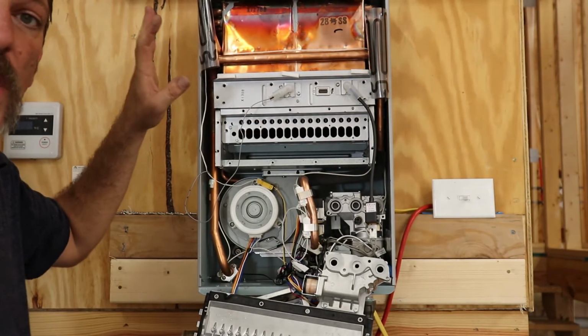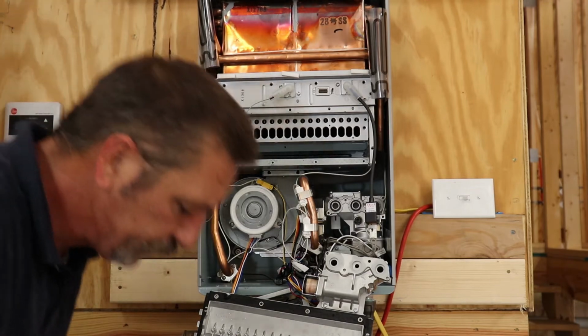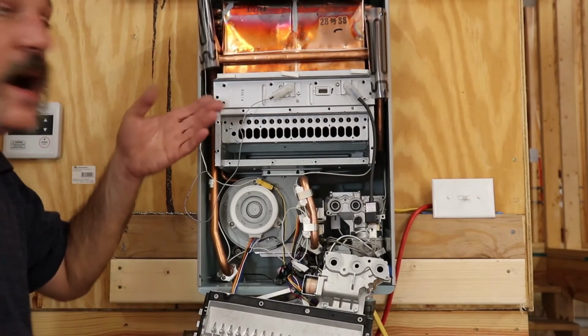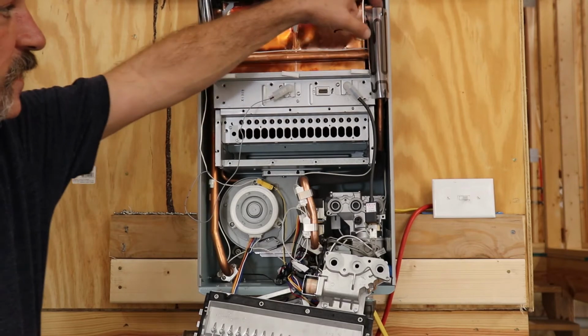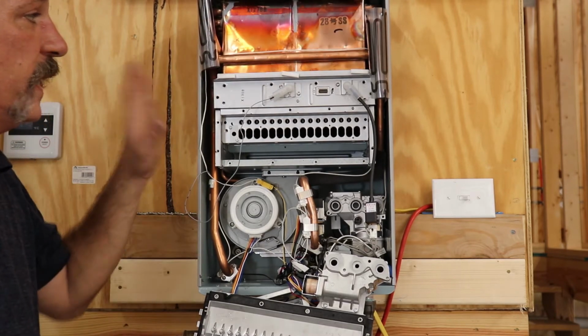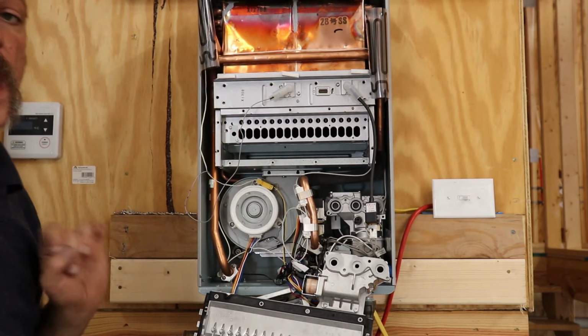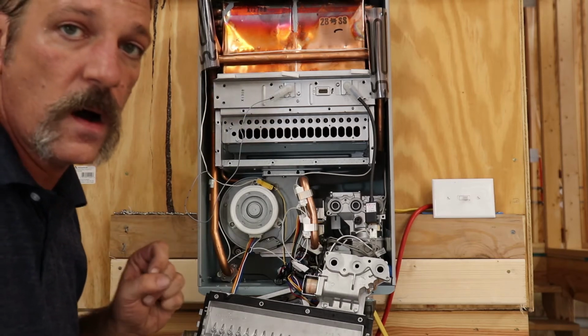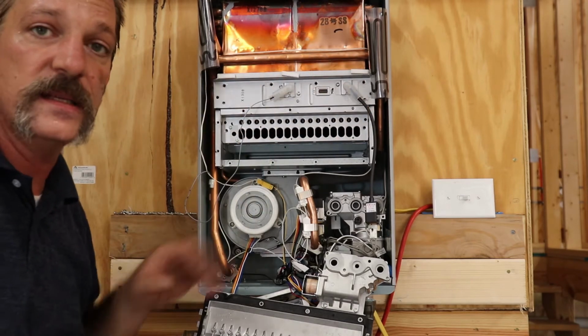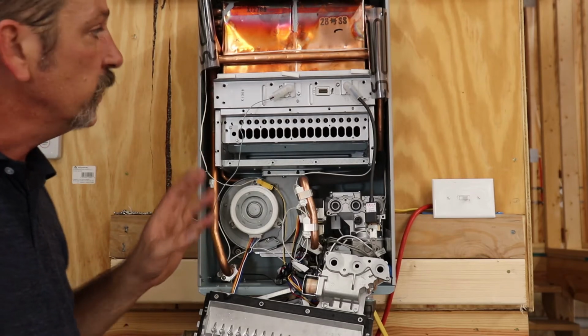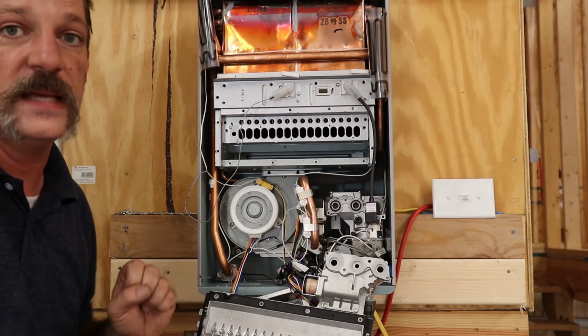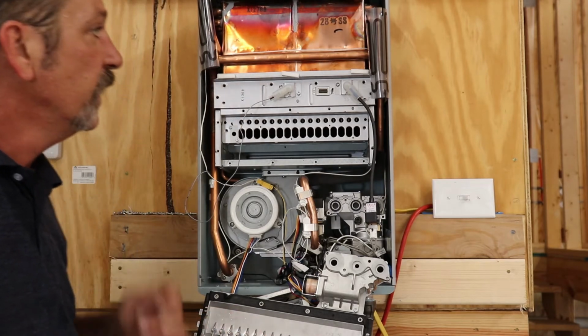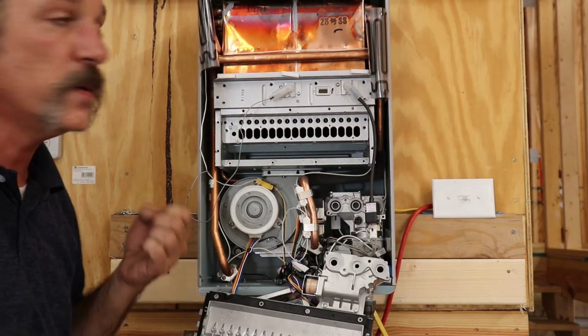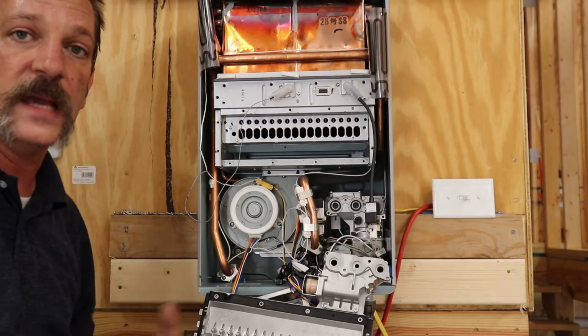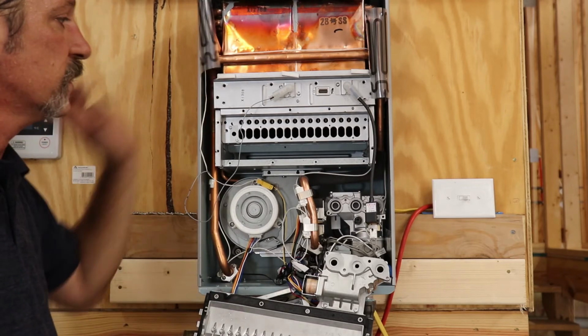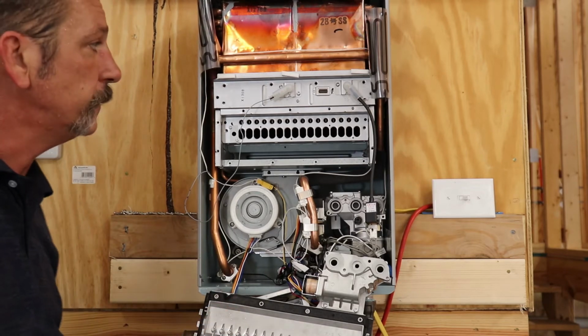This is your thermal overload protection. If this heater starts getting too hot, starts running away from us, this thing's going to pop and sever and the heater's going to shut itself down. This is a non-repairable or replaceable part. If you tear this, cut this, break this, damage this, the heater's done. You cannot repair it, you cannot replace it, and that's for safety reasons. It's a thermal overload or runaway protection, so if this thing just keeps making hot water for some reason, it'll snap that and shut everything down.